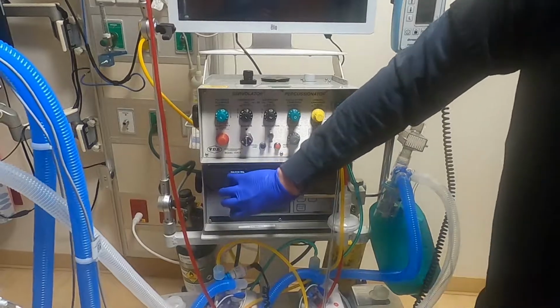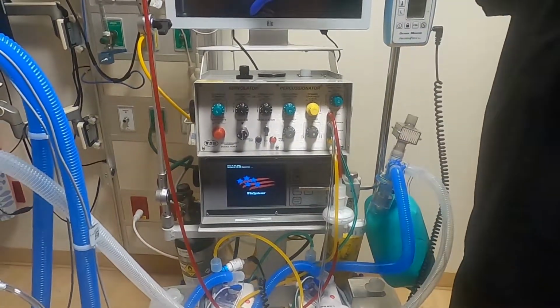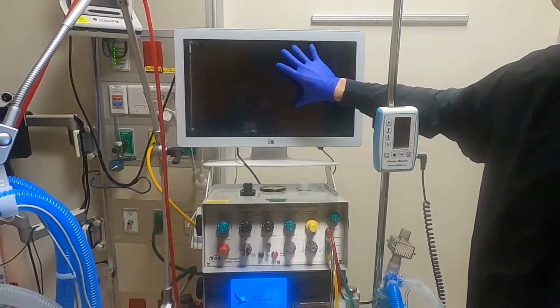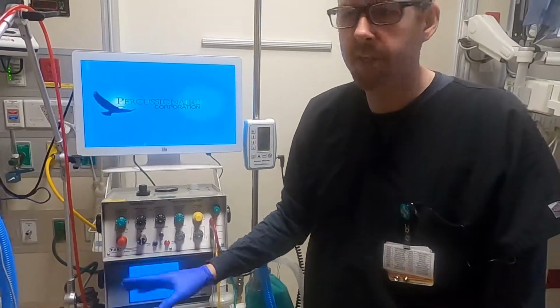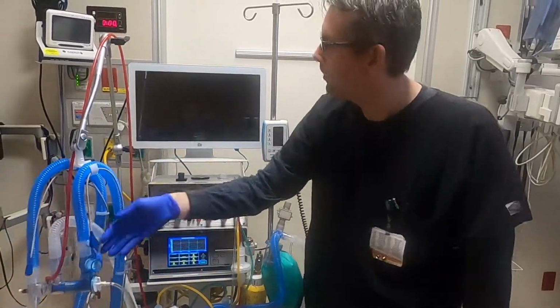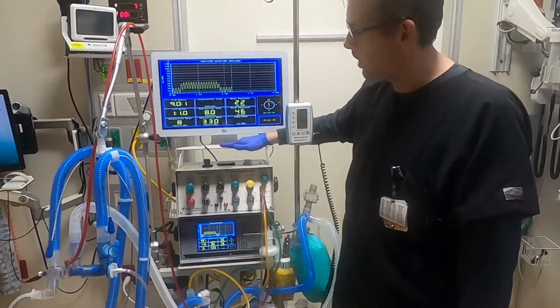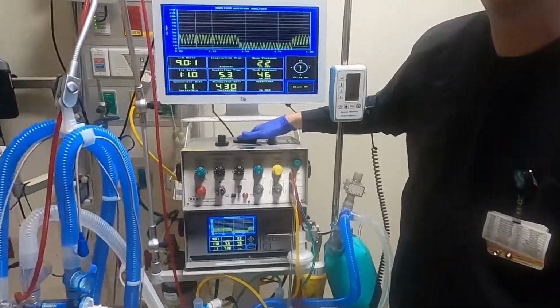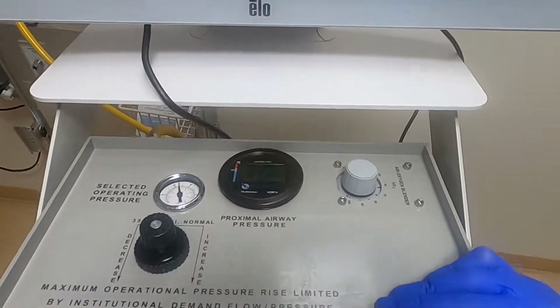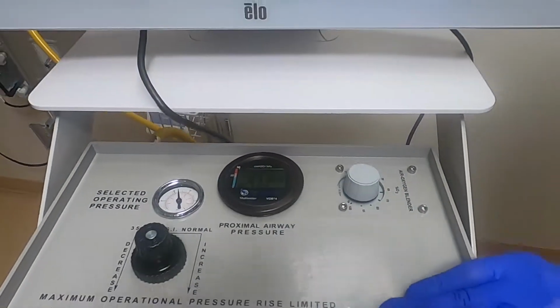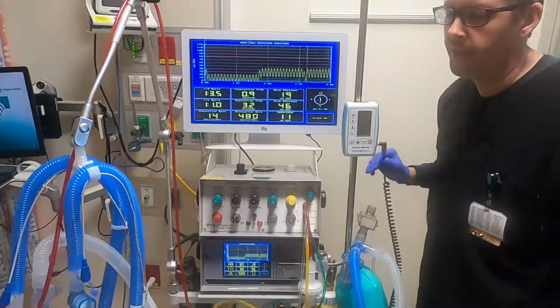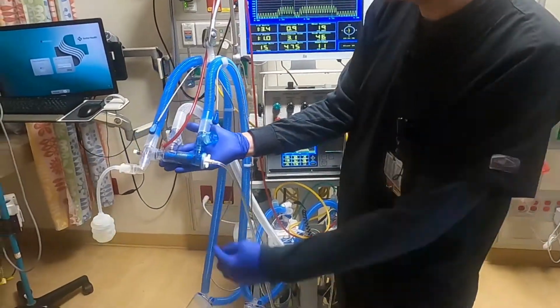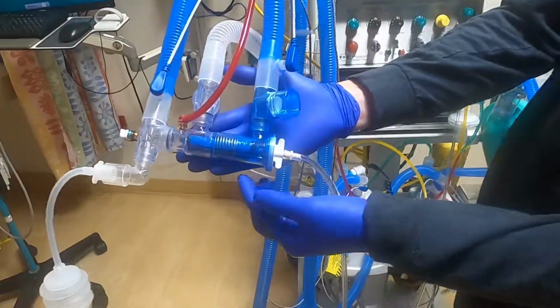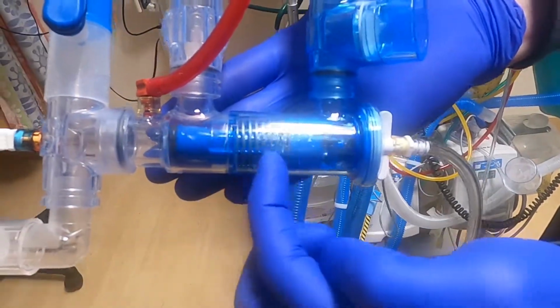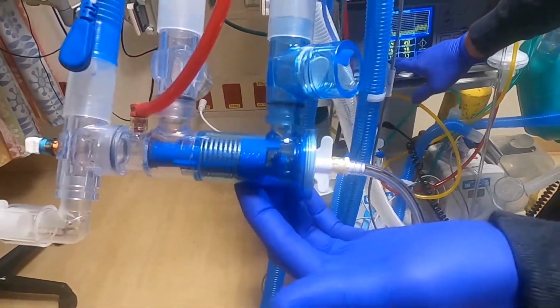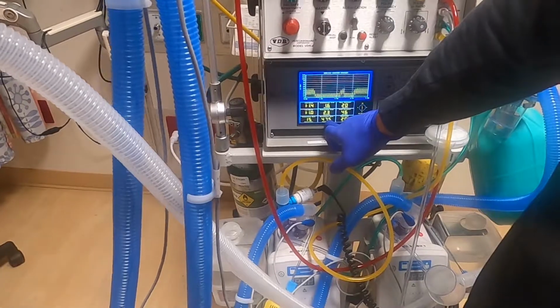So with this ventilator, the only electricity you will need is to have your monitoring readouts available. If your power goes down, it's still going to ventilate the patient. You just won't have your printouts, your readouts here. We can still monitor the pressures on your gauge. So that's one of the things about this machine. You don't need a battery. And as you can see, this is how the Phasitron moves. This is pulsating whatever we have set, and currently it's at 475 times a minute.